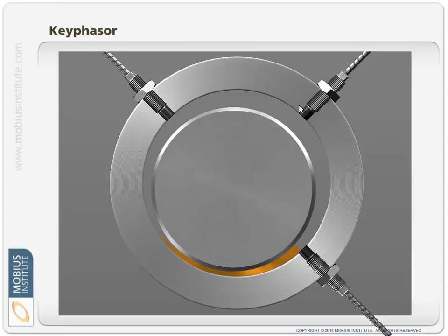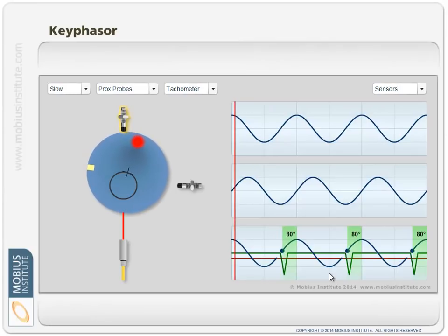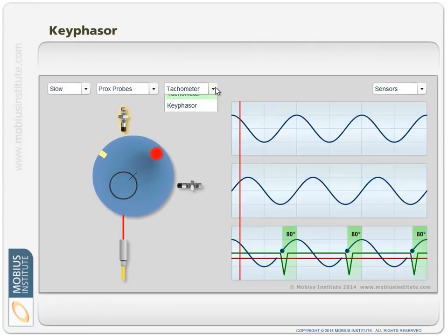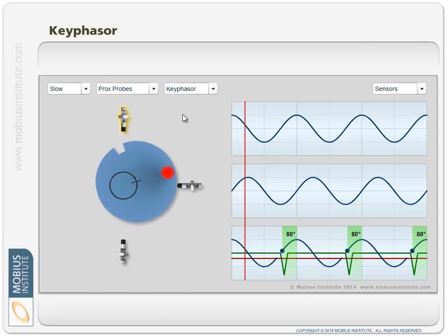We've got the X and Y, which will be typically in one plane, and then the Keyphasor, which will be axially in a different position along the shaft, along the rotor, because it's looking at the keyway. We might have these ideally located near every bearing, but we only need one of these just to get the once per rev. Lots more we could talk about all these things, but you know, we are pressed for time.